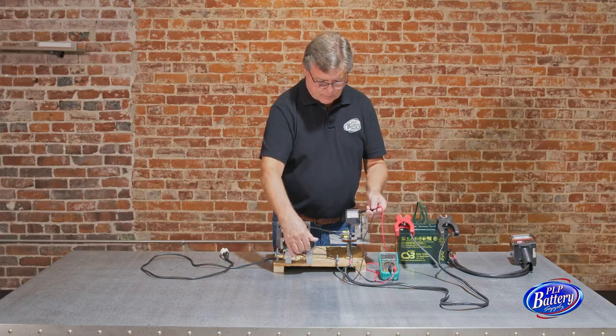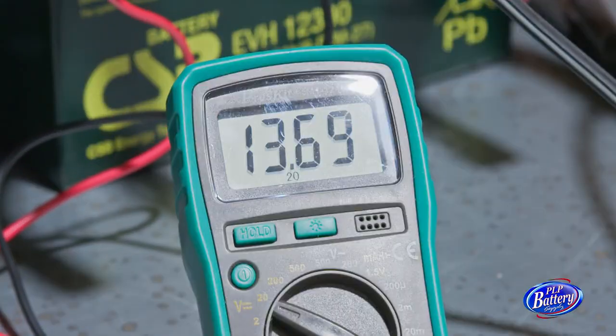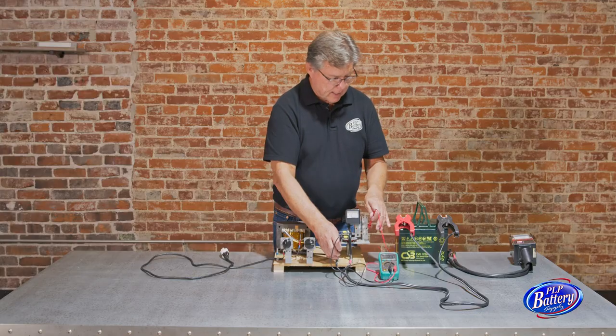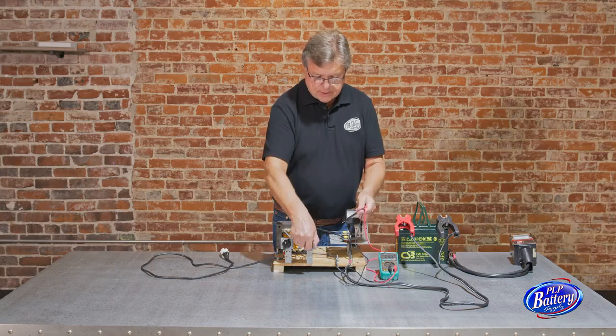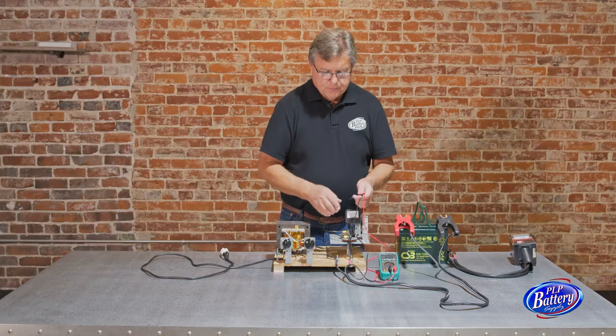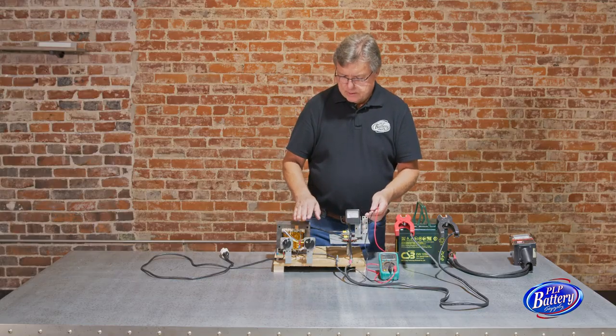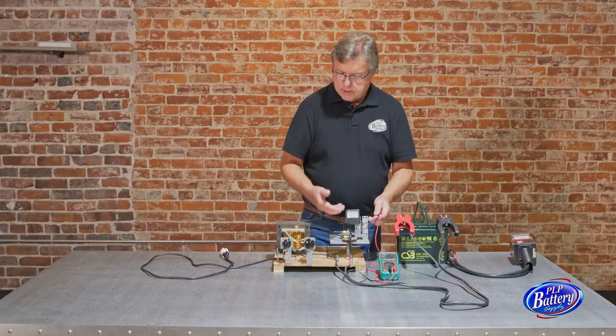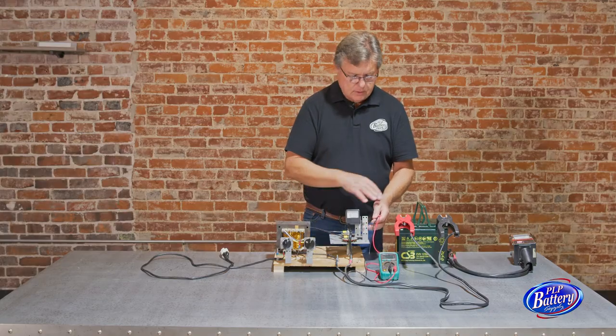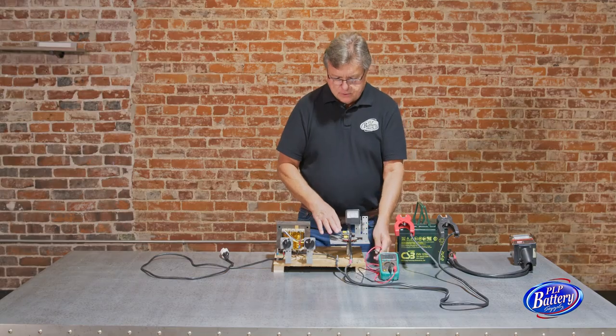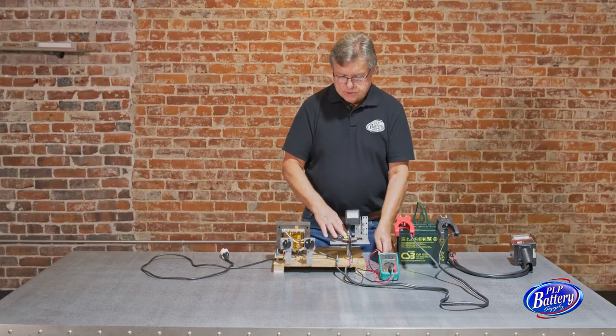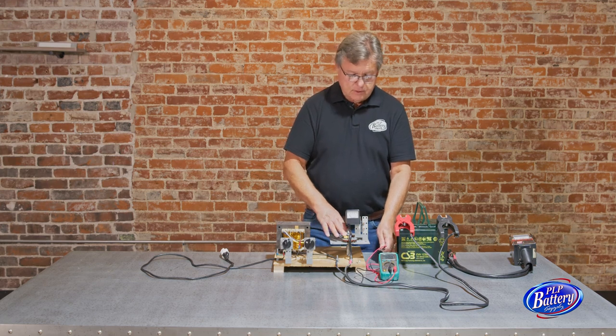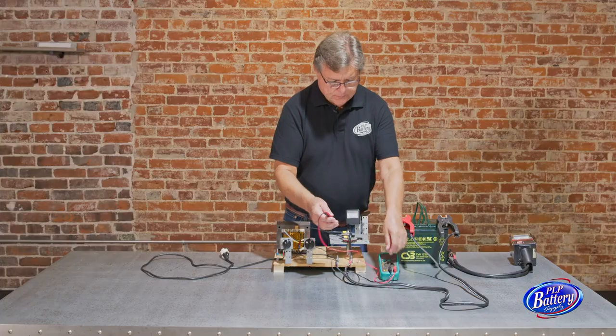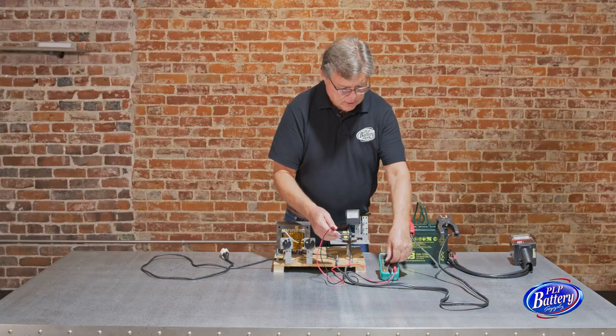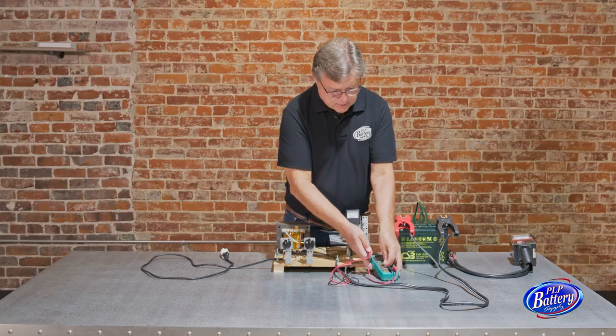Now if we bump it up, we're going to see that voltage spike. Now it's up at 13.6, and that's yielding that 16 volts at the battery DC that we were talking about earlier. So what you're going to see is the AC secondary is going to jump at each one of these rates. It's going to come up, commensurate with the setting and what you're expecting everything to do. And if you're getting good secondary voltage, if you're seeing that 11, 12 volts, if you're seeing that 13, 14 volts, but then you come down here and you're either checking at the battery or you're checking at the charger itself, we'll go back to DC voltage.